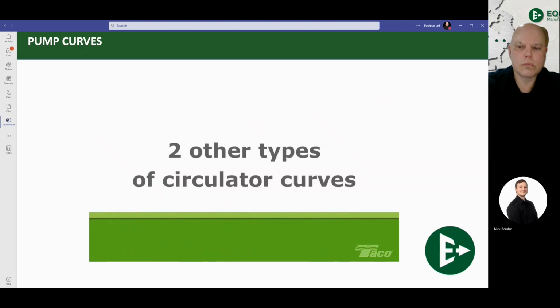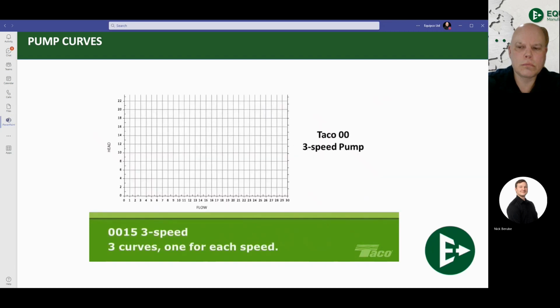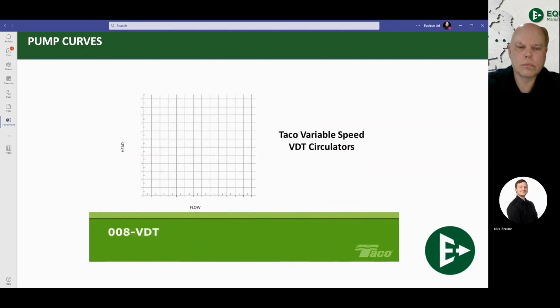That covers fixed-speed circulators, but we also need to look at the curves of two other types of circulators used in residential jobs. The first is the 3-speed pump. This curve is for the Taco 15 3-speed cartridge circulator. The curve for a 3-speed pump actually consists of 3 separate curves, one for each of the pump speed settings. The pump can operate on any one of these curves, but not between them. That brings us to Taco variable speed VDT circulators, which are different from all the pumps we've talked about so far. Here's the curve for the 008 VDT.